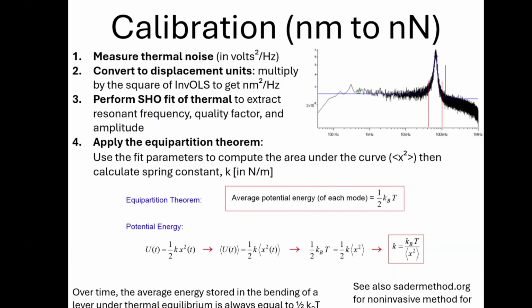K can be determined using the so-called thermal method. We just record the vibrations of the lever at all frequencies using the photodetector. These thermal fluctuations, due to Brownian motion, to molecules interacting with the lever, cause the lever to vibrate more at its mechanical resonance. So we measure the noise, use the invols to convert the noise in volts to noise in nanometers. We perform a simple harmonic oscillator fit of this thermal peak to extract parameters, and we apply the equipartition theorem, which just states that the energy associated with the vibrations is equal to 1/2 kBT, allowing us to solve for the spring constant. There's also a non-invasive way, meaning no force curve required, to obtain both invols and K from the thermal, called the Sader method.